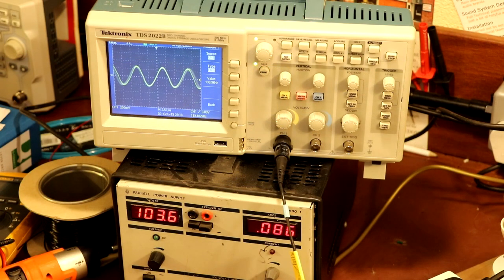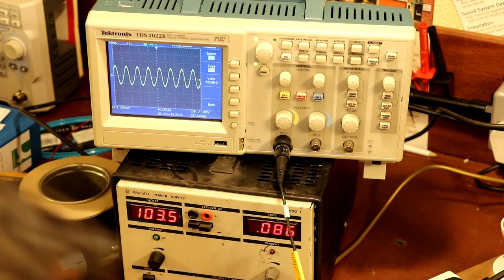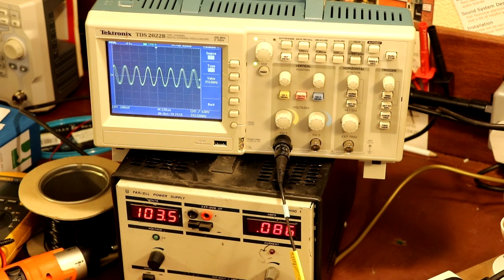Now if we do turn the frequency up a bit, we tend to lose the oscillation. Let me just go up to the next range. Yeah, and we've lost it. Oh, we got it back. So let's see what the calibration's like on this one. This should be around 300 kilohertz, and it's coming up as 295 kilohertz.